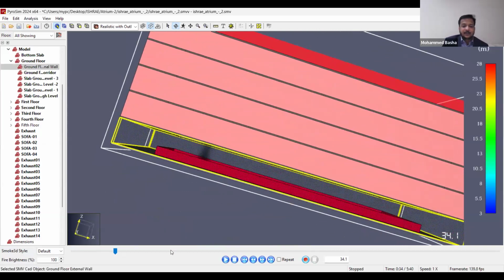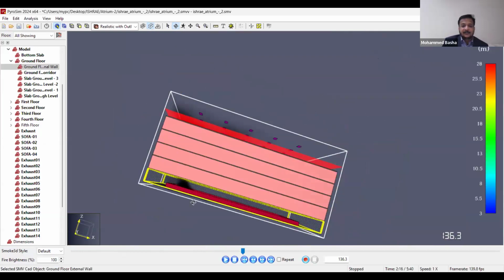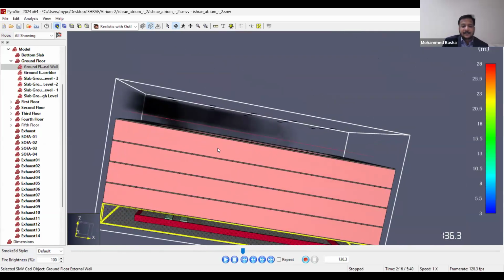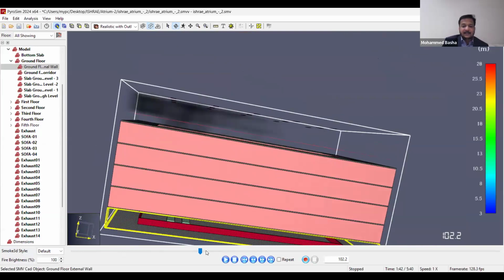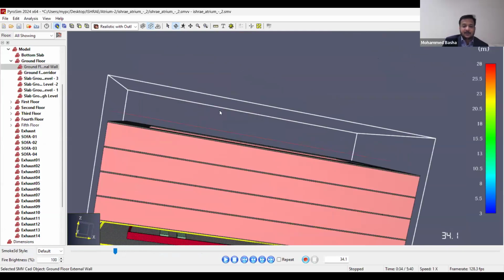You can see the fire is developing, right? And basically I activated this, but you will not see the exhaust here. Why? I put a control that the fan should operate after 50 seconds. Because the smoke detector has to detect, right? Then only the fans will operate. So up to 50 seconds, you will not see the exhaust outlets. Just wait. After 50 seconds, you will start seeing the exhaust outlets.